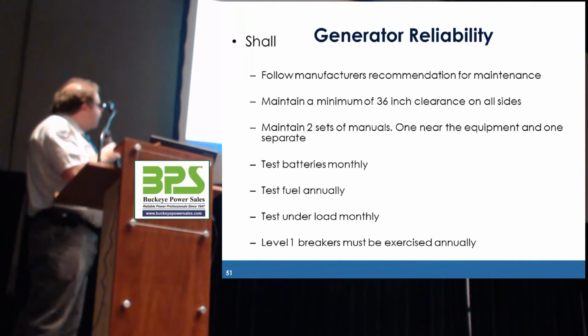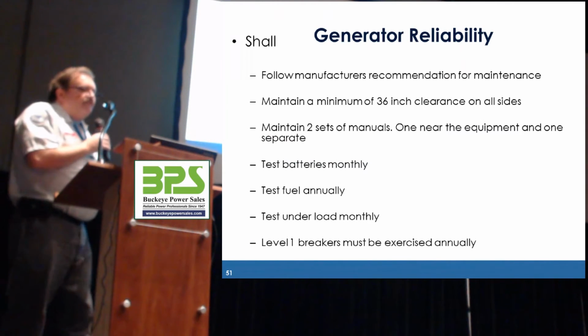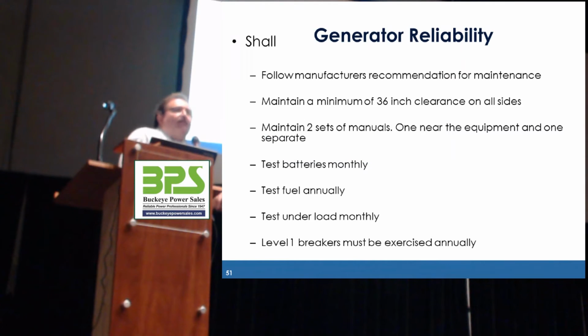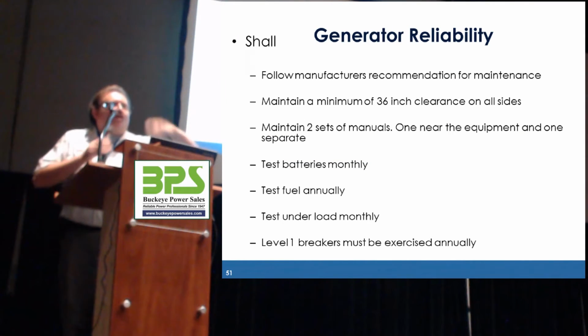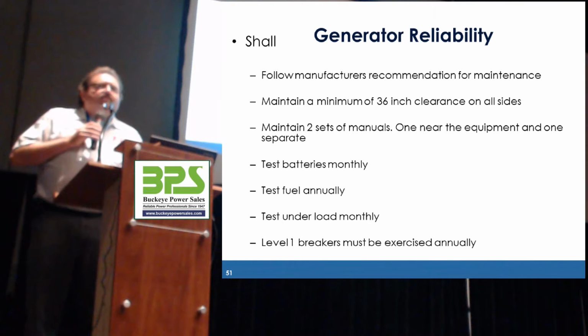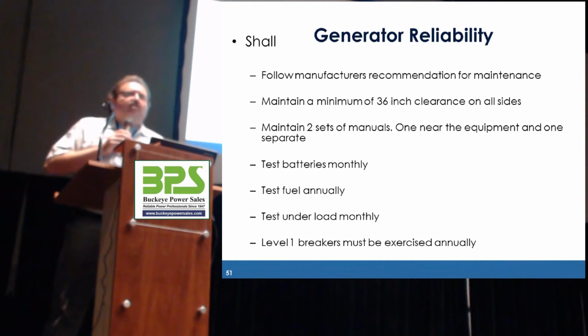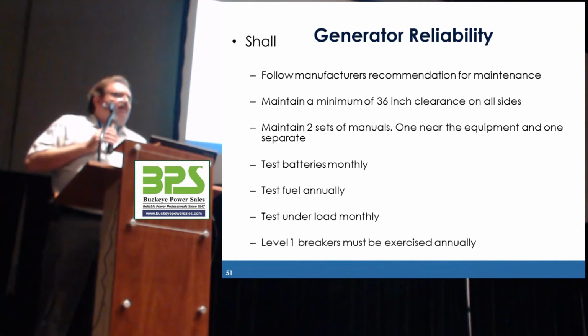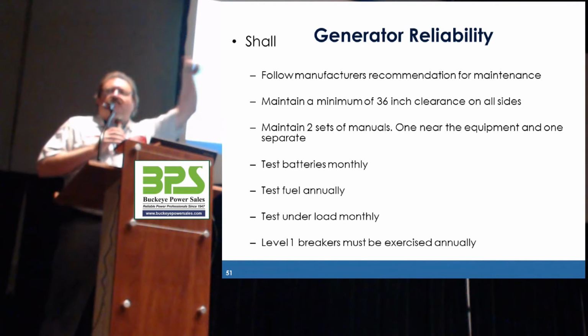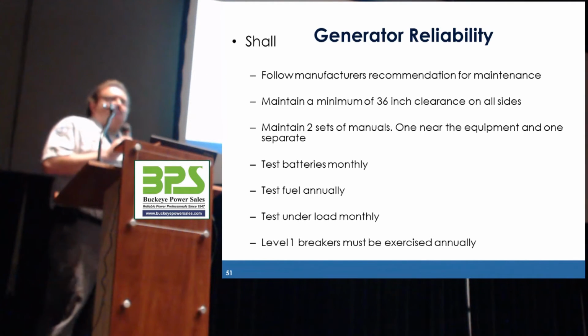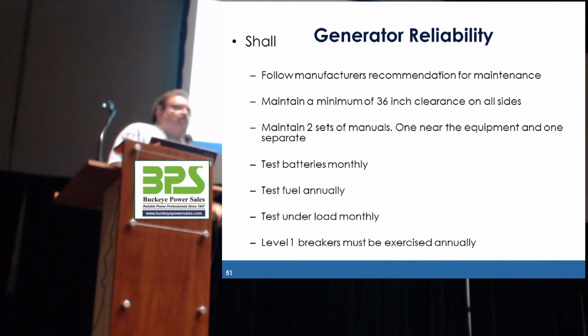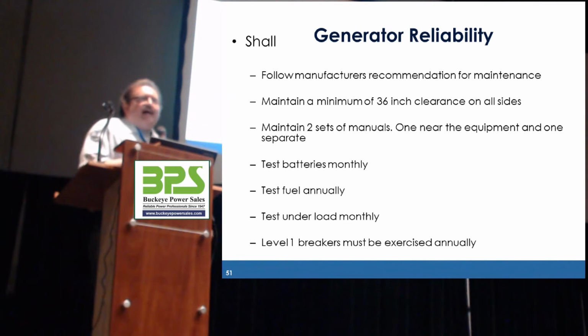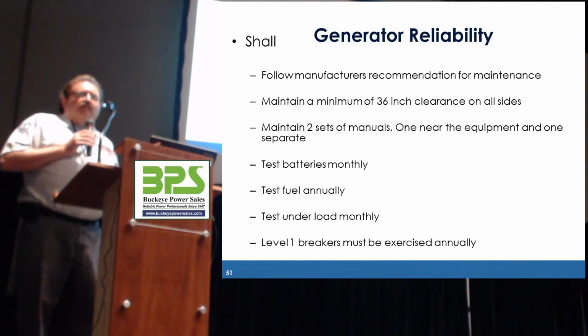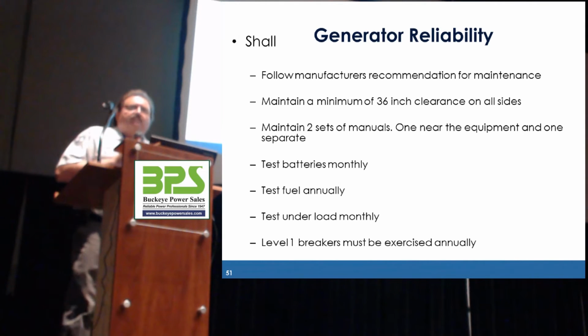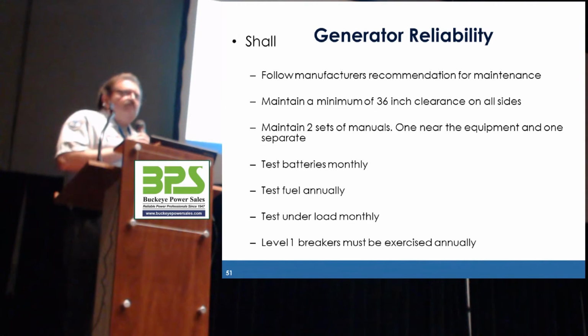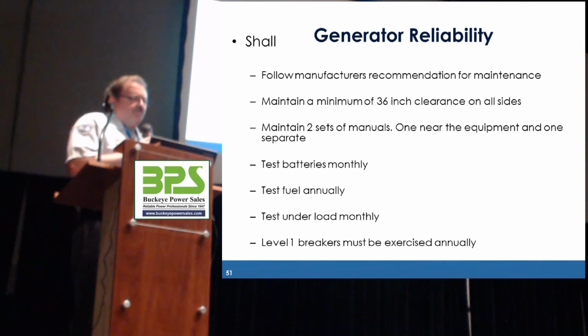The code says you shall follow the maintenance. It says you shall have 36 inches clearance on all sides. That means the transfer switch has to have 36-inch clearance in front of it. The generator has to have it on all sides. Big box stores are the worst. You go into the electrical room and they've got display racks and product all stacked up in front of the electrical gear. The folks here, that's not going to be an issue, I'm sure.